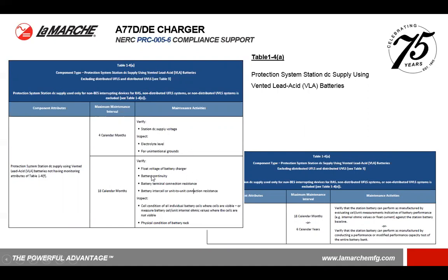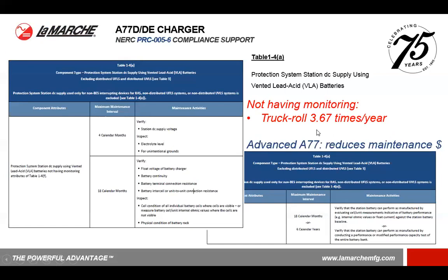18 calendar months later, you'd be coming back to, again, look at the float voltage, check battery continuity, connection resistance, etc. Even at the 18 calendar month or really 6-year interval, you're essentially performing a battery performance test. So not having monitoring is a heavy penalty because you have to visit the site so many times. This averages to almost 4 visits a year. The advanced features of the A77 can reduce your maintenance costs.